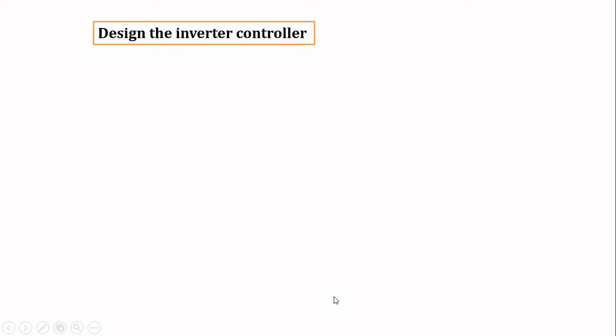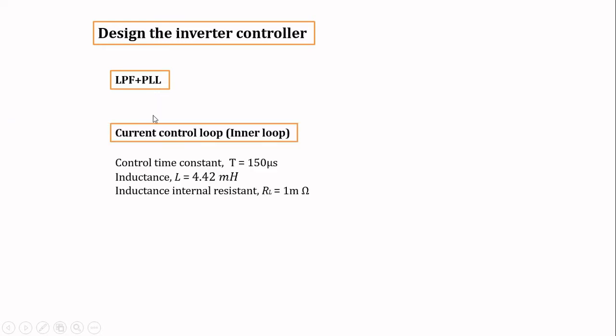Second, we design the controller. The control of the grid-connected inverter includes a low-pass filter, a phase-locked loop, and a current loop controller. We need to choose various control time constants. I have chosen 150 microseconds. The inductance equals 4.42 mH as designed previously, and the internal resistance equals 1 mΩ. Therefore, Kp equals 29.5 and Ki equals 6.67.